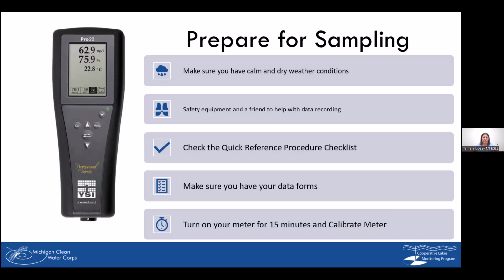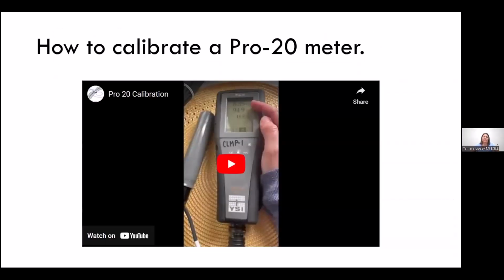Make sure you have all your data forms, and then turn on your meter for 10 to 15 minutes, and then calibrate your meter. Here's how to calibrate your Pro 20 meter. Calibrate, by the way, means that you're checking the moisture inside that cap, which should be somewhere around 100% because it's got a moist sponge, and it's kind of like a little sauna in there. And you're checking to make sure that your meter is operating correctly and measuring around 100%.